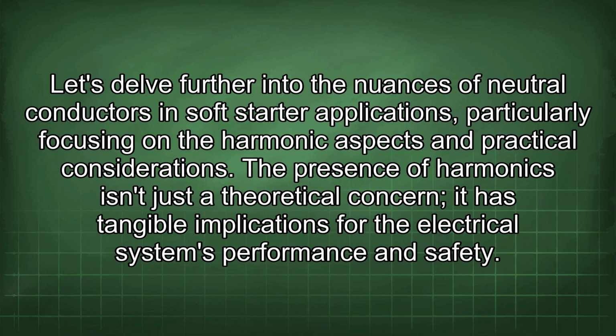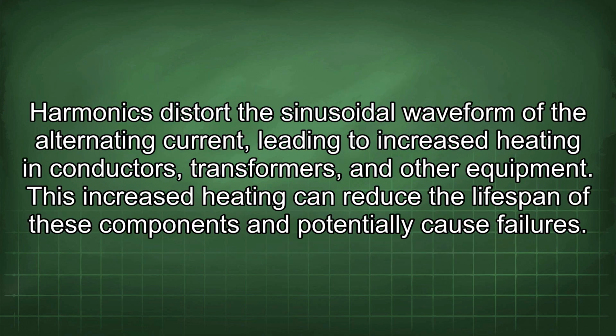Let's delve further into the nuances of neutral conductors in soft starter applications, particularly focusing on the harmonic aspects and practical considerations. The presence of harmonics isn't just a theoretical concern, it has tangible implications for the electrical system's performance and safety. Harmonics distort the sinusoidal waveform of the alternating current, leading to increased heating in conductors, transformers, and other equipment. This increased heating can reduce the lifespan of these components and potentially cause failures.